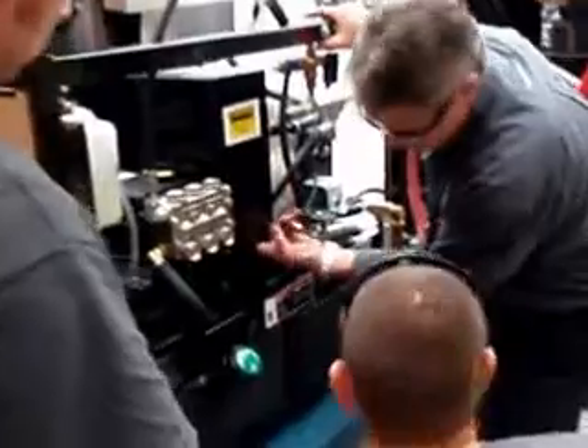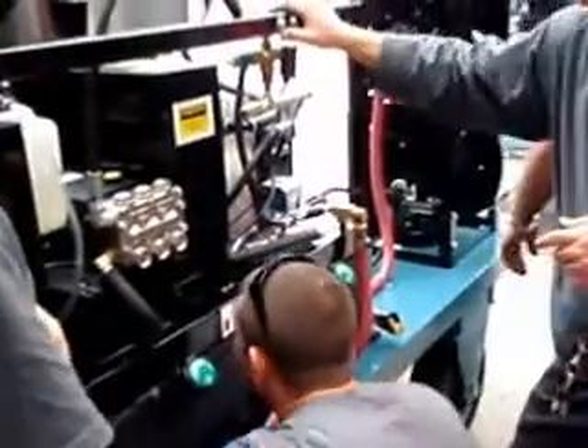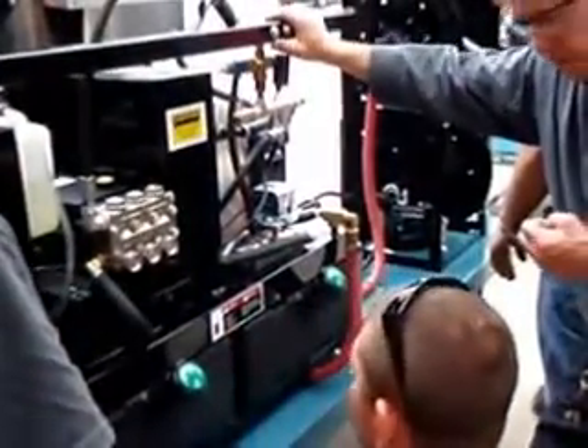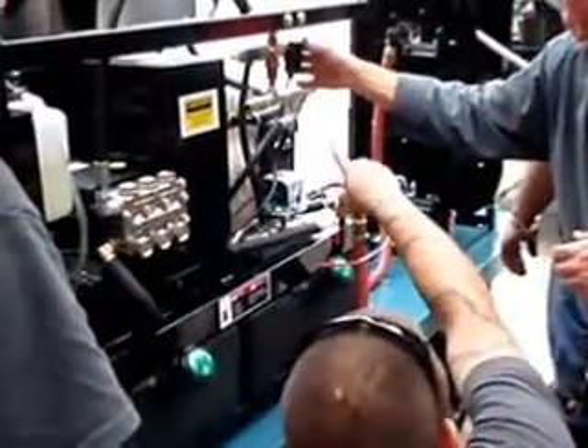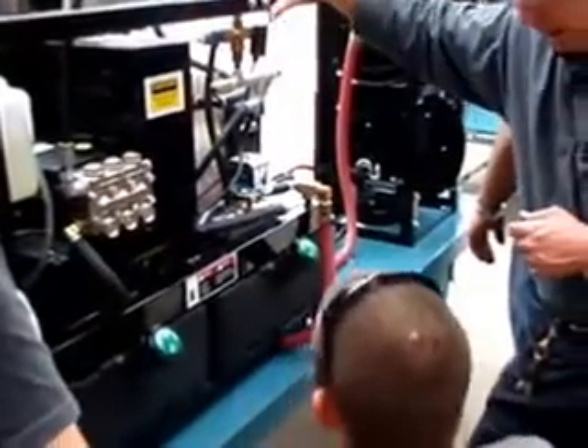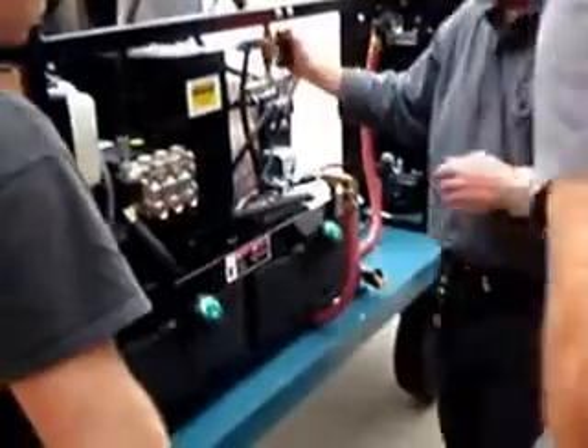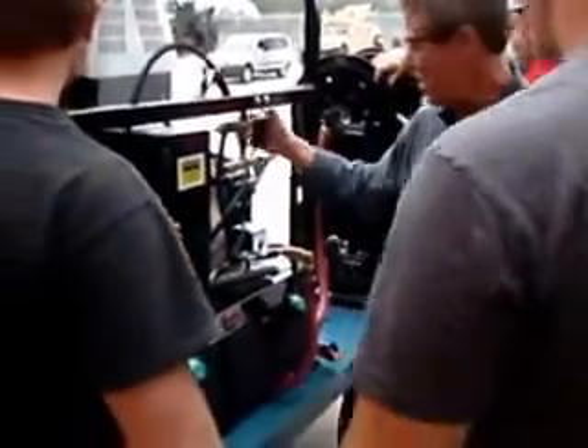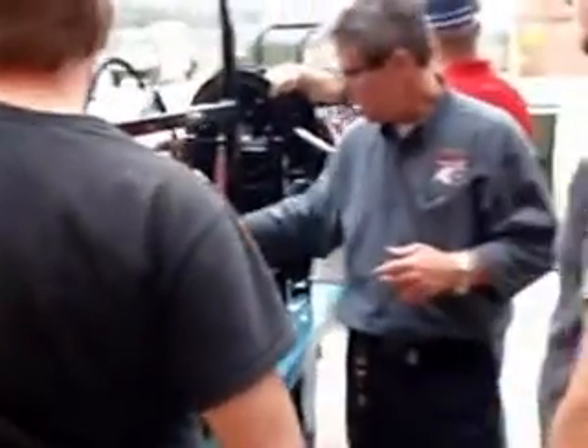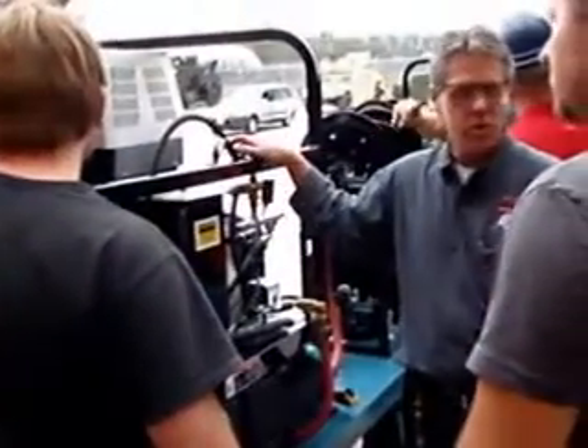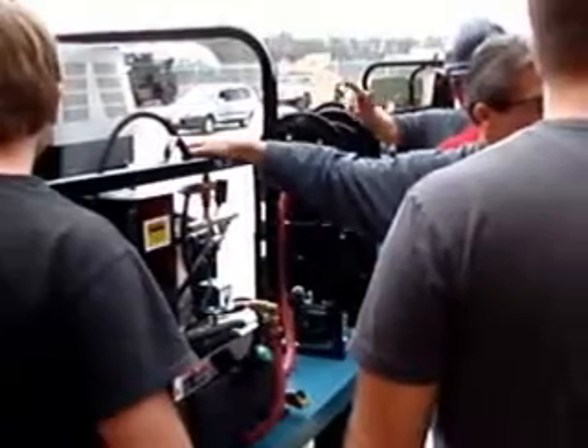You see right there, you've got a clutch drive system - like a centrifugal clutch? No, it's an electrical clutch. Now that's activated by the flow switch? By the pressure switch, right - exactly, pressure switch. These controls, guys - they break them and I fix them, that's why I get so many questions. Pressure switch controls your clutch, float switch controls your burner solenoid. So you don't have to shut it down every time you need to turn it off or something - exactly.